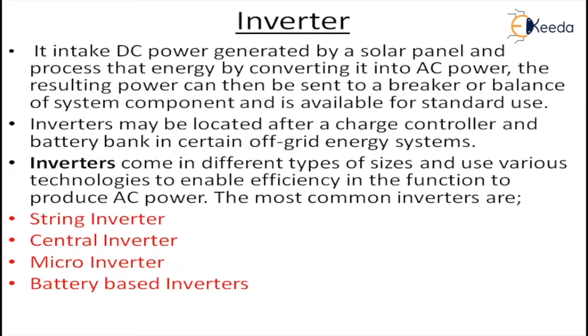Next is the inverter. All loads connected in systems are usually AC loads, but a solar PV system produces DC. So we require one conversion — DC to AC — which is done by the inverter. The inverter is always located after the charge controller and battery bank in an off-grid energy system. It is not situated on the roof; it is in a closed room, so IP protection is rated accordingly. There are many types of inverters: string inverter, central inverter, micro inverter, battery-based inverter, and now even nano inverters, which are placed at the back of the panel.